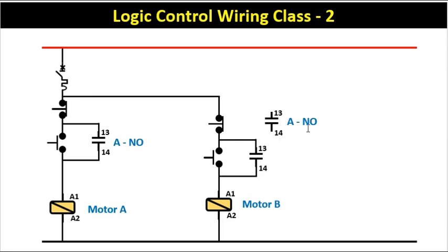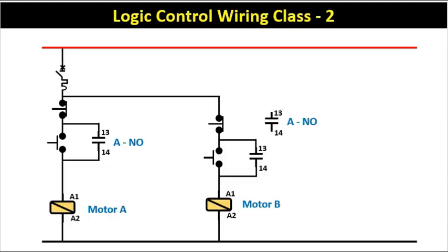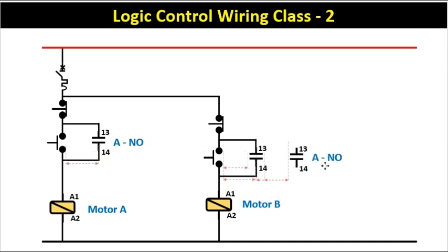Now we have to add the NO contact back into this circuit. This NO contact was used previously in the condition where, if we start motor A, then motor B should start automatically. So this NO contact is being used to turn on motor B. We will connect this NO contact in parallel to the start push button.